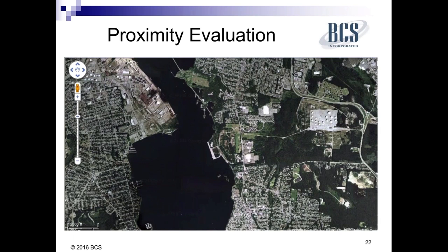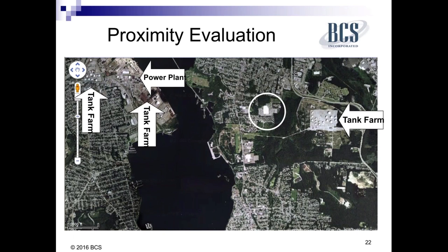Proximity. Why don't you go ahead and click through, because I've got a little animation on this. In that circle in the center is a big data center. On the location, yeah, there you go. In this case I'm asking a customer, is this one of your must-have requirements for site selection? You need to be within a few hundred yards of salt water and only a few feet above sea level in a storm surge area. Better have some good tank farms on all sides of you, be isolated, better have some power plants, all those risks we talk about.